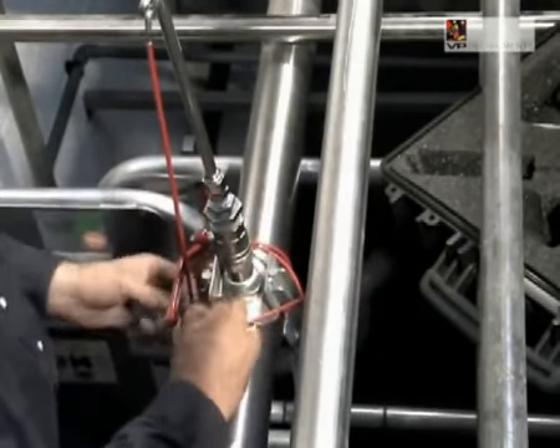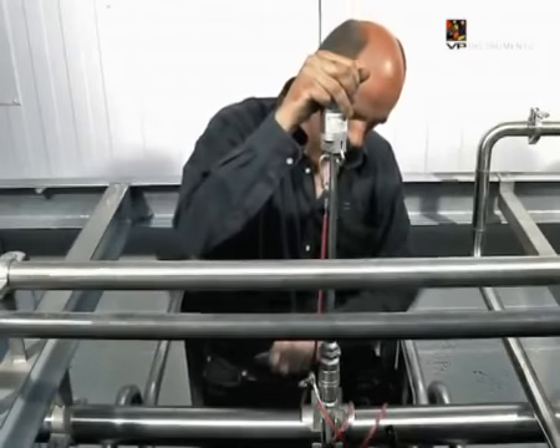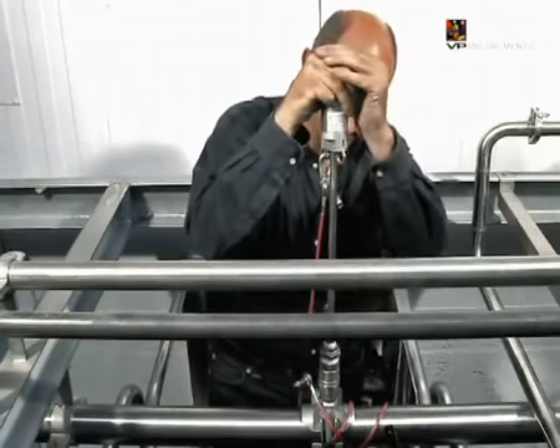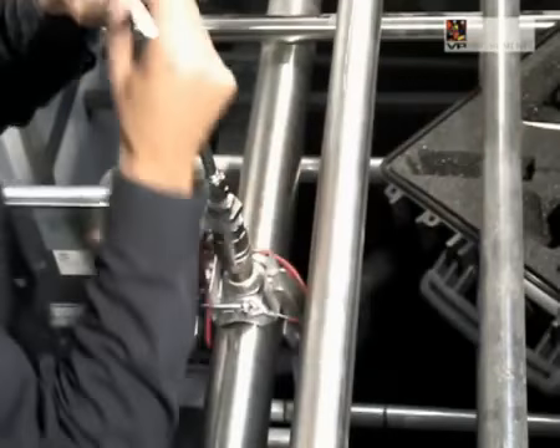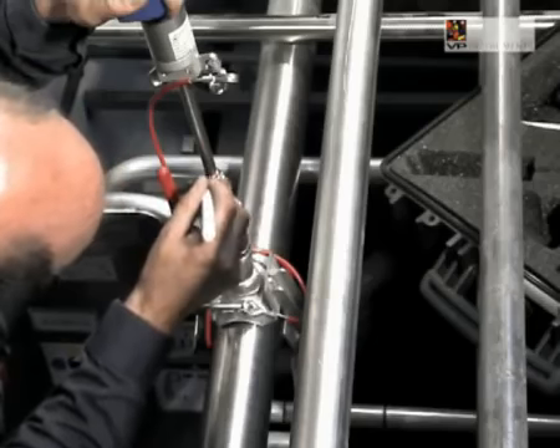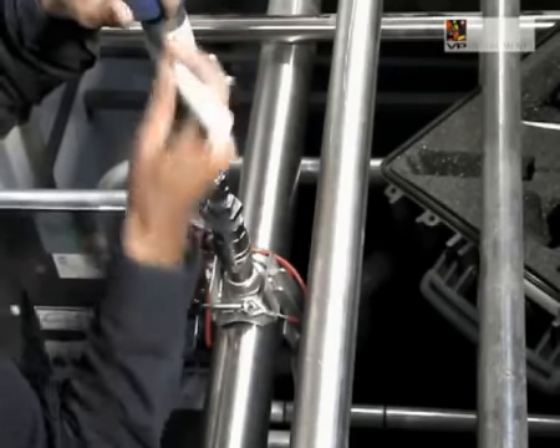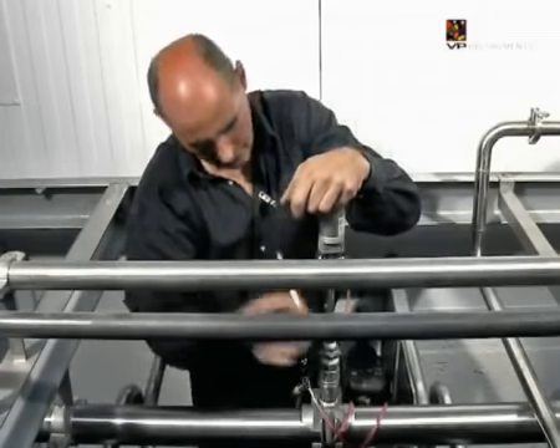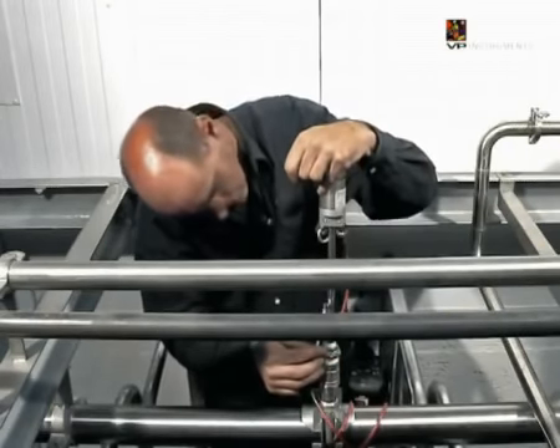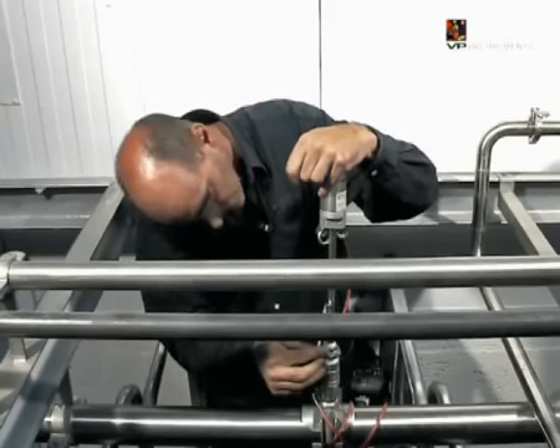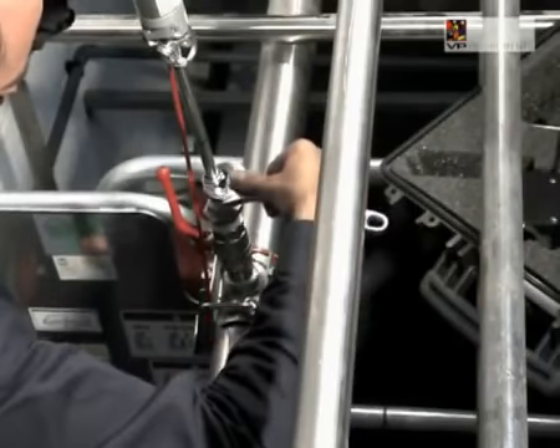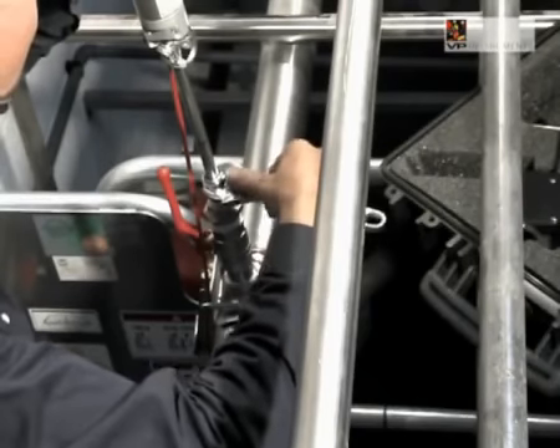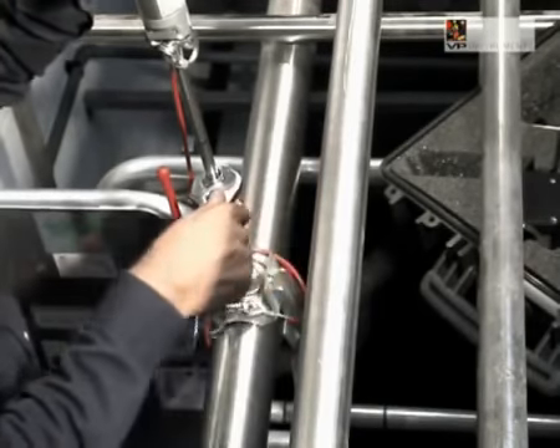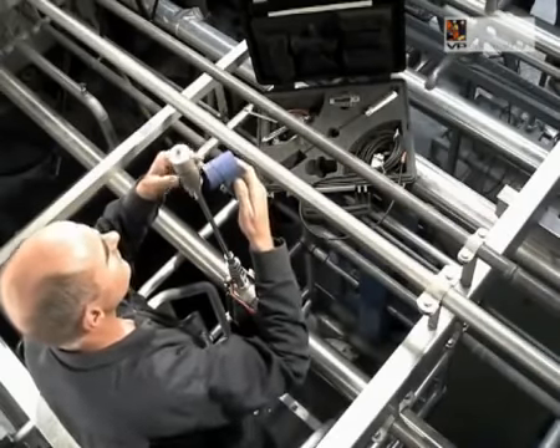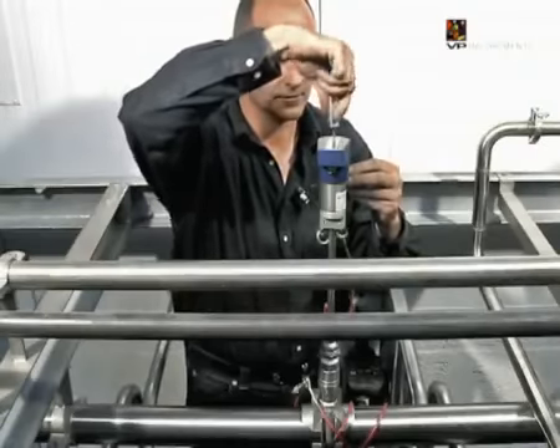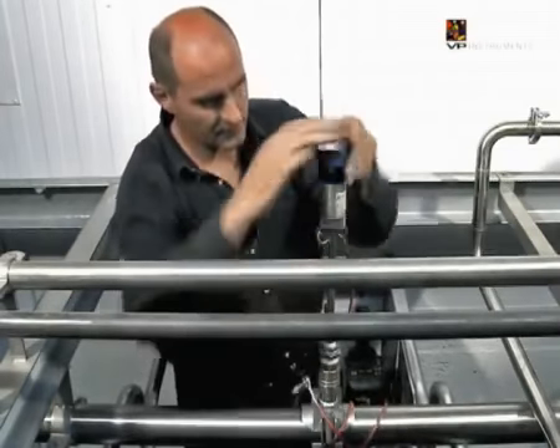Keep the ball valve closed and insert the sensor module. Mount the safety line and secure it. Open the ball valve and gently push the VPFlowScope in until it reaches the bottom of the pipe. Keep the VPFlowScope in place and place a mark on the probe. Retract the probe by half the pipe diameter. Use a tape measure to check the distance between the mark and the top of the compression fitting.